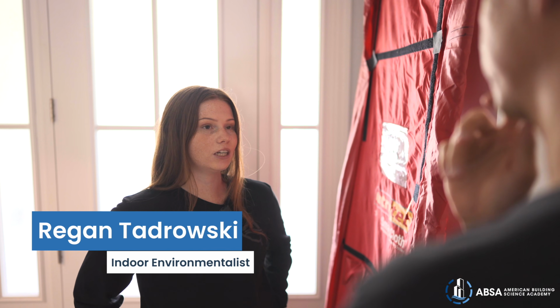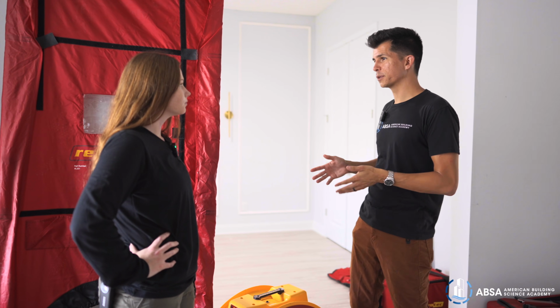What's this about? This is a blower door. It's going to help us figure out how airtight the spray foam is that they just installed. We're going to go around, first visually look for any openings in the spray foam, but then this is going to depressurize the home. That way we can find some of those harder to see spots, and we can use a smoke pen and a thermal imager to really hone in on those areas. So that takes care of the spray foam, which is awesome.